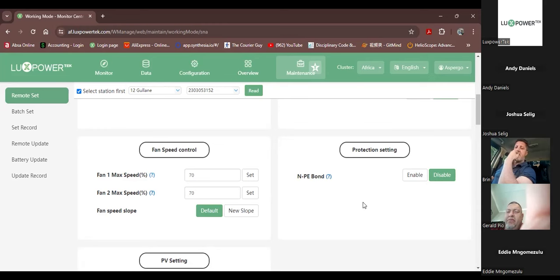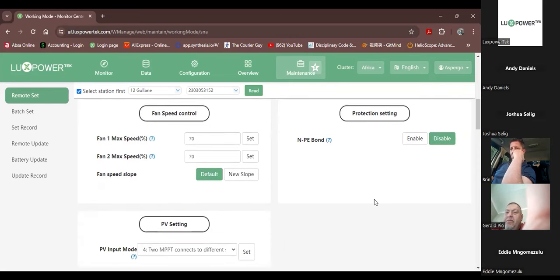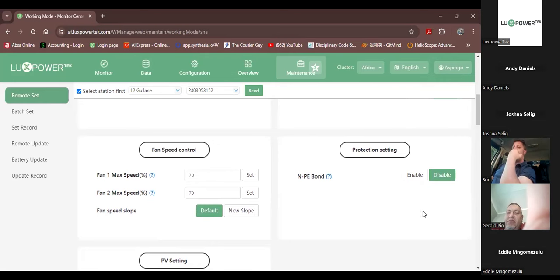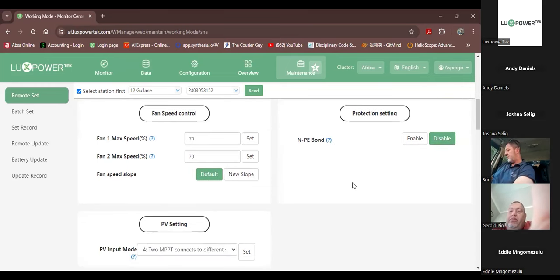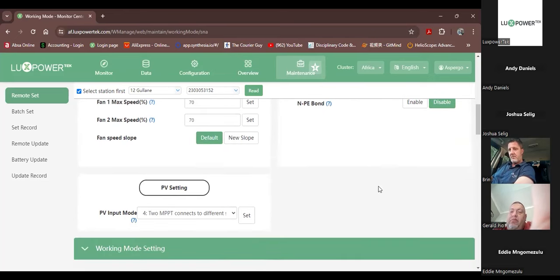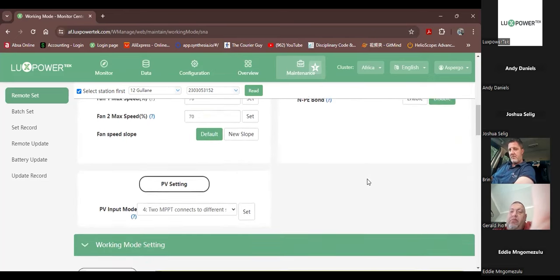What this allows you to do is when the machine is in the on-grid mode, it will assume that the bonding is already done at the municipal transformer and there's no bonding required on the EPS output. And only when the machine goes to off-grid mode and you've enabled this, will it close the bonding relay inside the machine, and then you should get 0 volts between neutral and earth on your output.